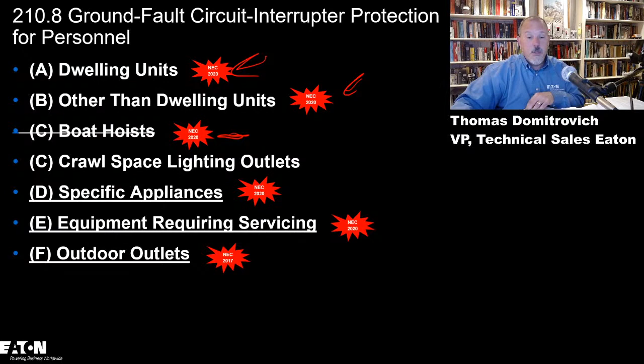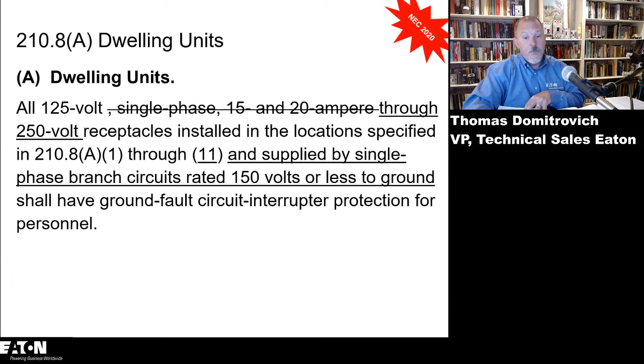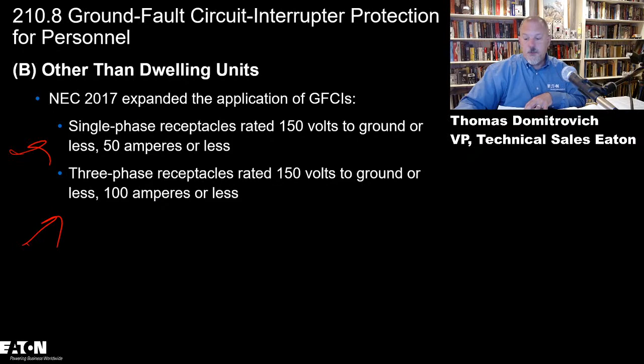Now be mindful that we expanded beyond 15 and 20 amps in A and B. In A, it's any circuit in those areas. In B, it's any of the circuits up to 50 amps single phase, 100 amps three phase. So we moved single phase up to 50, and three phase up to 100.